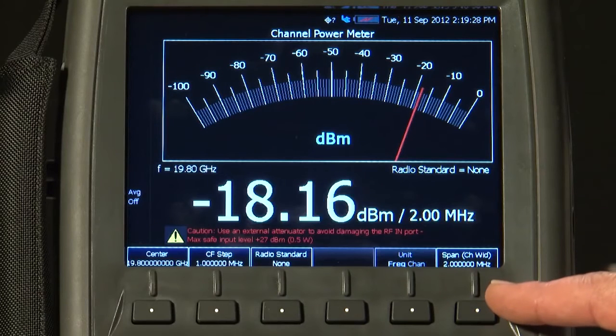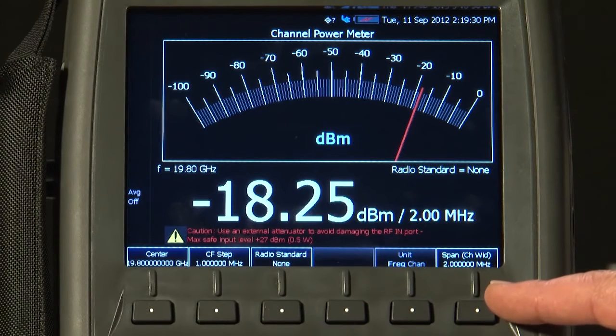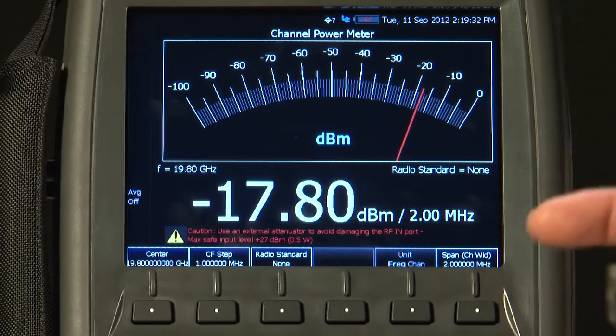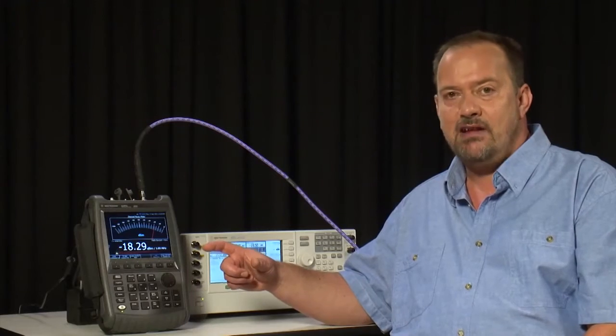And on the right here, we have set the span or channel width to 2 MHz. So that is the bandwidth within which we are measuring the RF power.